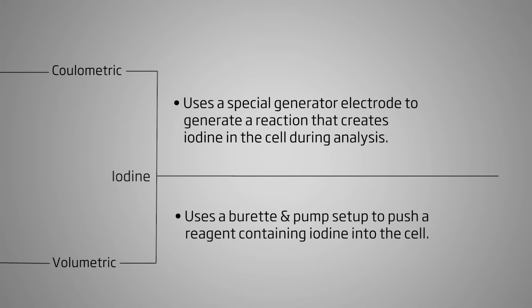Coulometric titrators have a special generator electrode that drives an electrolytic reaction that creates iodine directly in the cell. Volumetric titrators have a pump that adds the reagent containing iodine directly to the titration cell. This difference is very important since the coulometric titrator can accurately generate small quantities of iodine by applying small amounts of charge, while the volumetric is more suitable for samples with higher amounts of water.